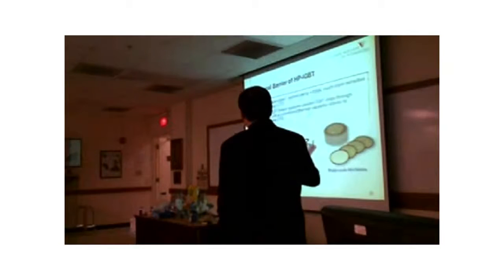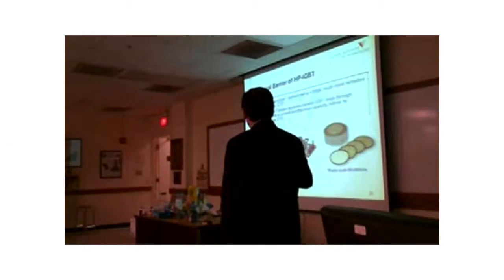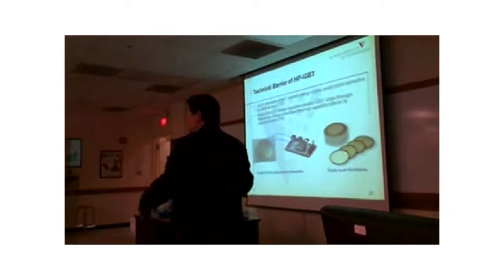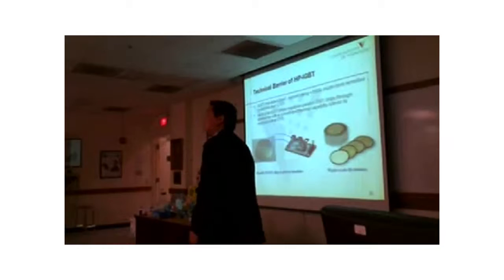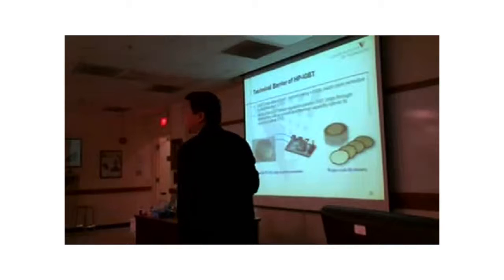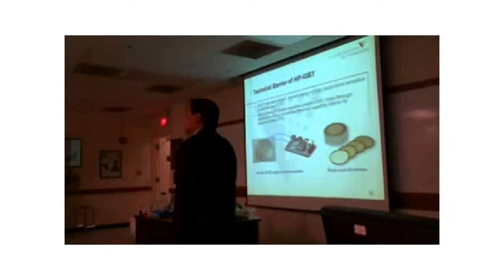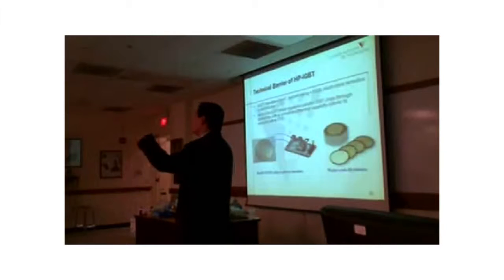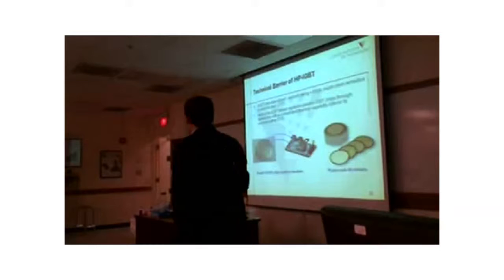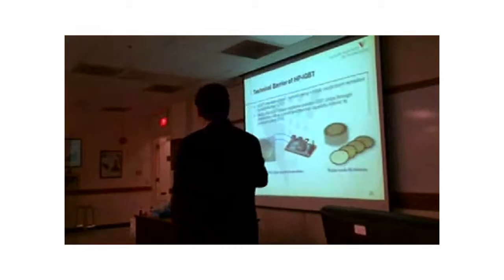But compare how people make thyristors: we make the entire wafer as one thyristor device. That's how thyristors can carry 5,000 to 6,000 amps in each of those hockey puck kind of packages. You may ask, wouldn't thyristor wafers also be sensitive to defects? Not as much, because the thyristor cell structure has a much larger dimension and much deeper junction depths, at least one order of magnitude larger than the IGBT, so they're not as sensitive to those crystal defects on the wafer.